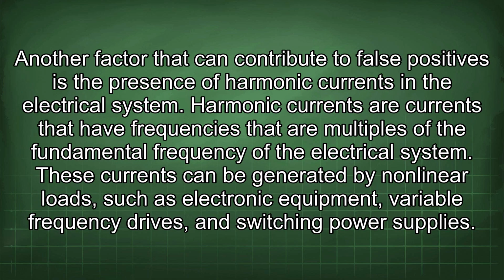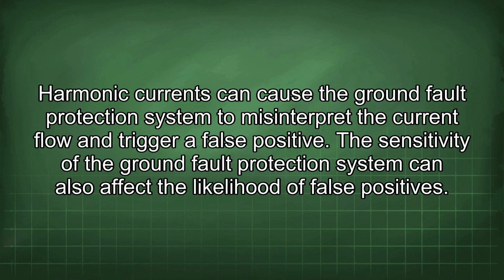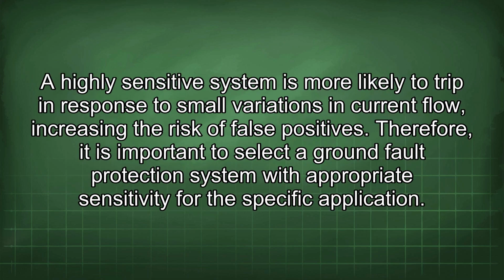Another factor that can contribute to false positives is the presence of harmonic currents in the electrical system. Harmonic currents are currents that have frequencies that are multiples of the fundamental frequency of the electrical system. These currents can be generated by nonlinear loads such as electronic equipment, variable frequency drives, and switching power supplies. Harmonic currents can cause the ground fault protection system to misinterpret the current flow and trigger a false positive. The sensitivity of the ground fault protection system can also affect the likelihood of false positives. A highly sensitive system is more likely to trip in response to small variations in current flow, increasing the risk of false positives.